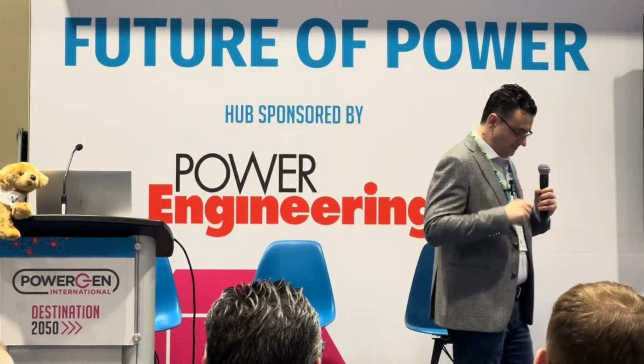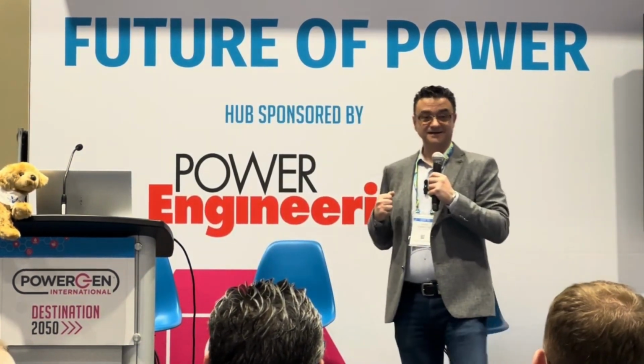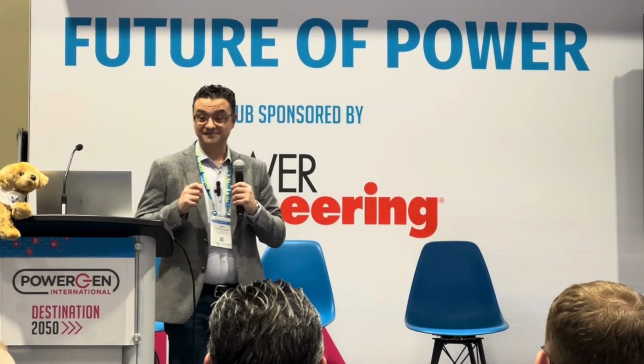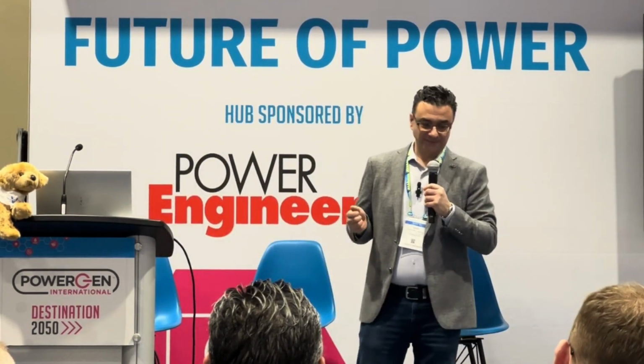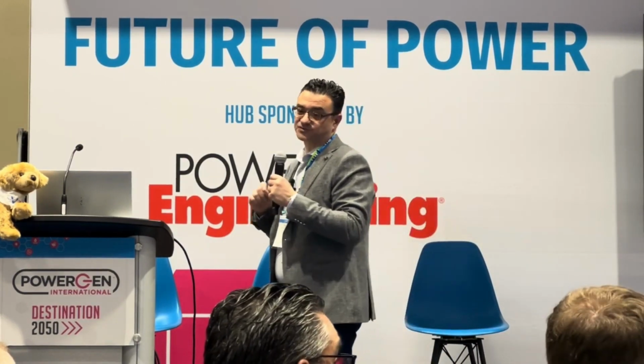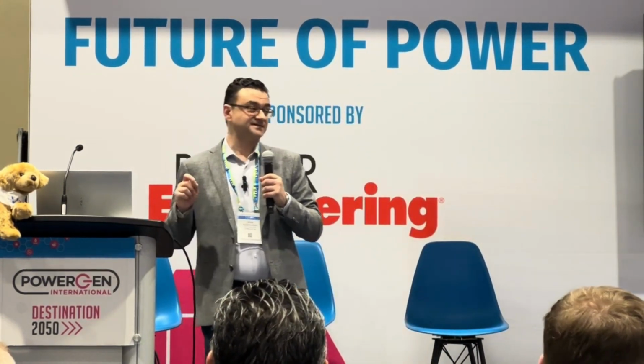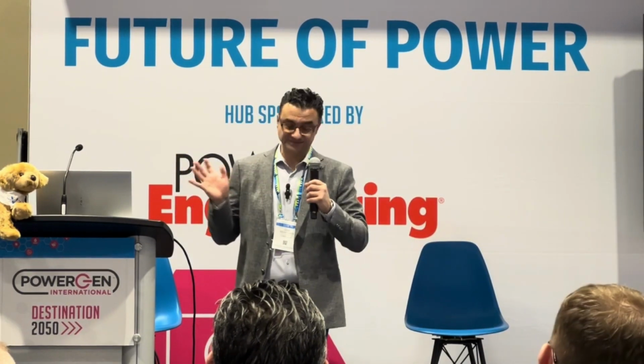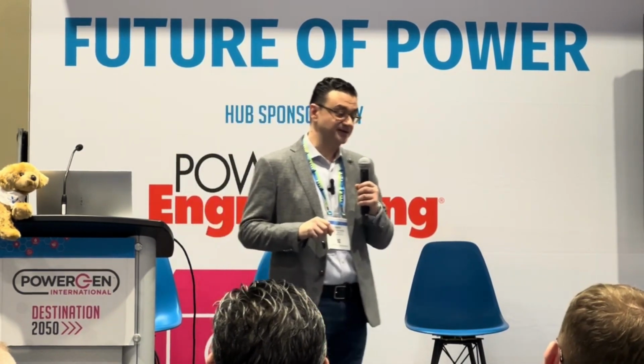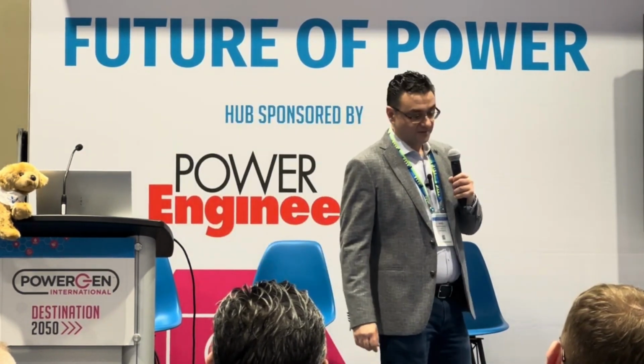An example: I'm Canadian, I'm from Canada. We have a 600 volt system, and a lot of our motors are actually rated at 575 volts because they're widely available. So when the utility starts to ramp up from 600 volts, 610, up to 650, which is something that they do occasionally, you can start blowing out motors.